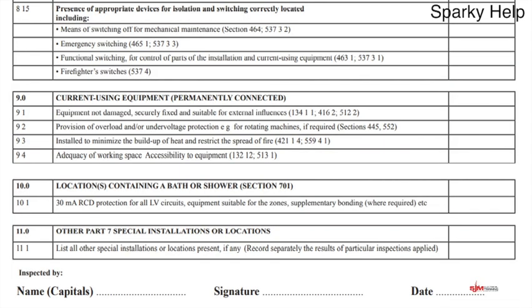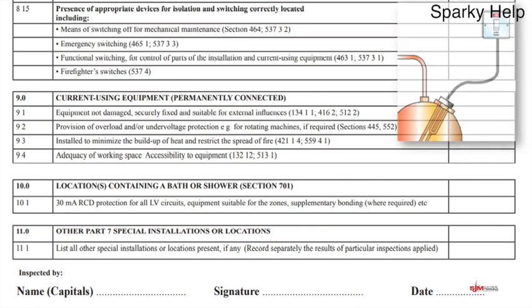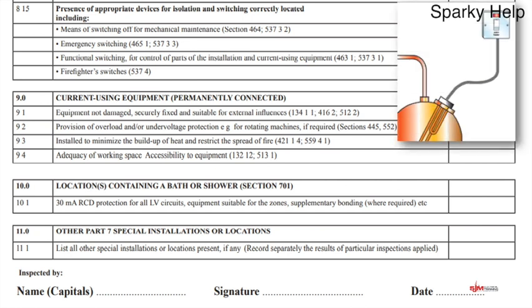Presence of appropriate devices for isolation and switching, correctly located. Means of switching off for mechanical maintenance sounds quite commercial and industrial, but it's simply about — can you actually switch things off? An immersion heater, for instance — can you put an isolator next to it? Cookers — have you put an isolator switch so you can turn it off, and is it within the correct distance? So that non-skilled people, if they need to clean them, can safely isolate it.